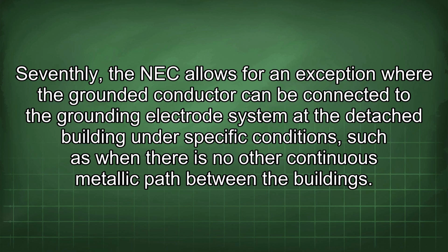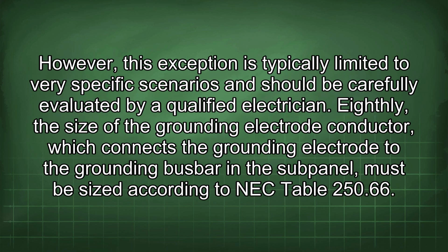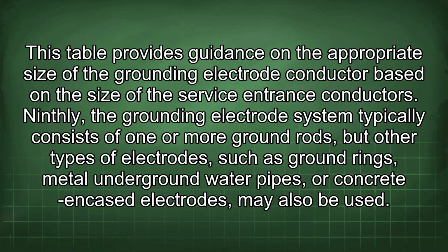at the detached building under specific conditions, such as when there is no other continuous metallic path between the buildings. However, this exception is typically limited to very specific scenarios and should be carefully evaluated by a qualified electrician. Eighthly, the size of the grounding electrode conductor, which connects the grounding electrode to the grounding busbar in the subpanel, must be sized according to NEC Table 250.66.